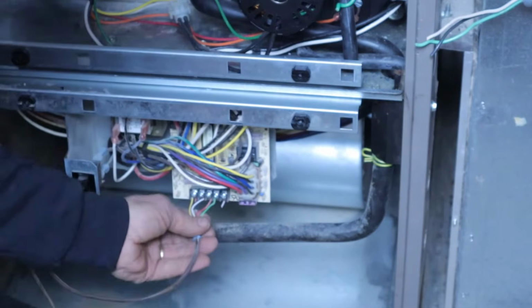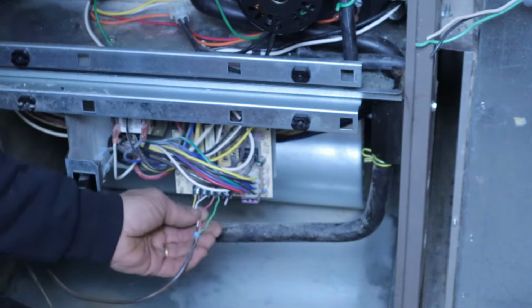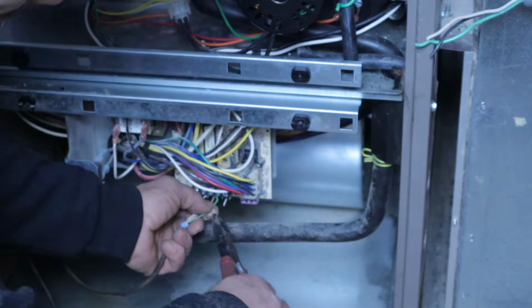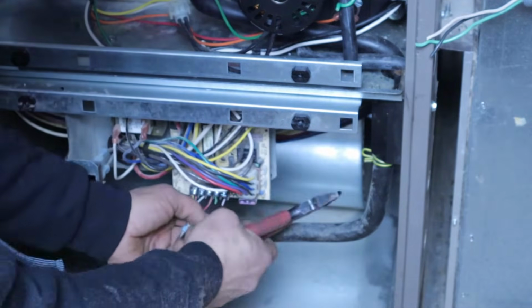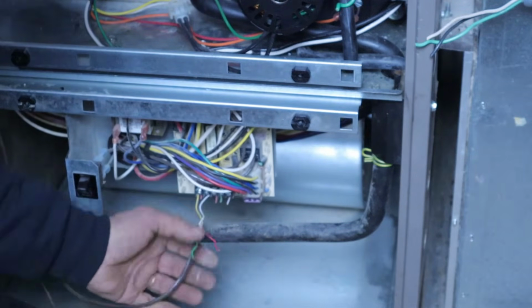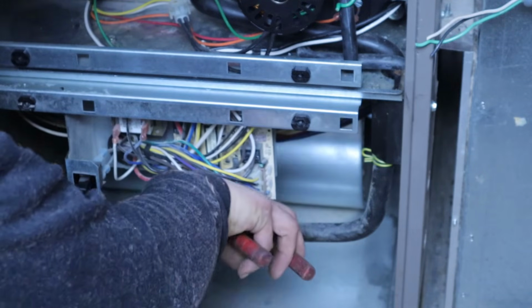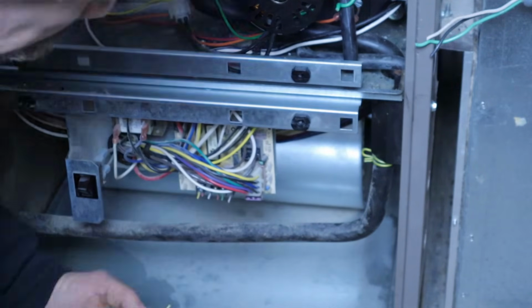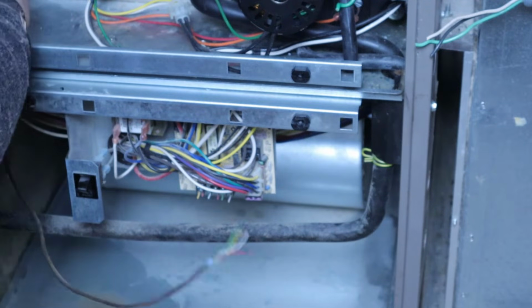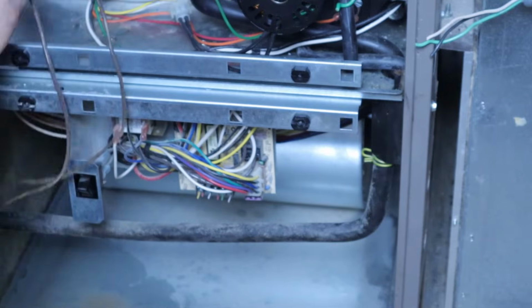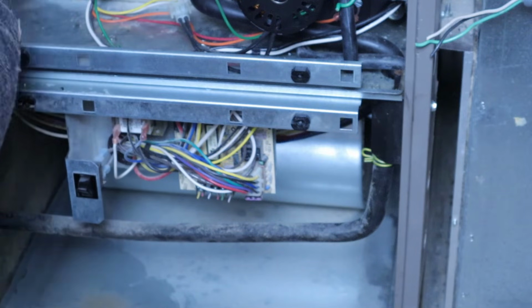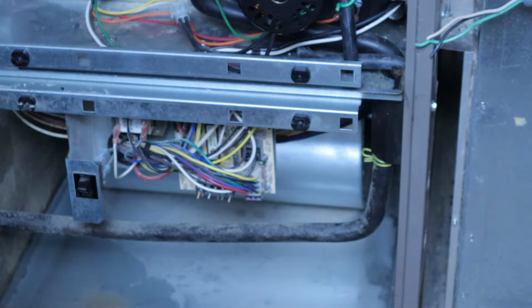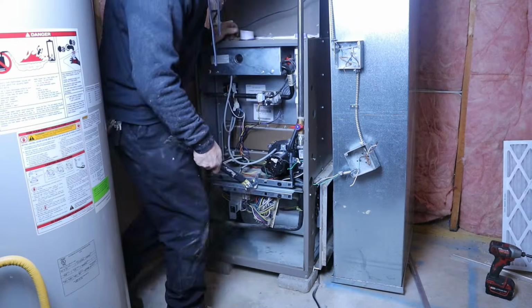And we have our 4 thermostat wires that go up to the thermostat. We have our green, that's our fan function on the thermostat. We got our red, which is our power, our white, which is our heating, and the yellow that is our cooling. So we got that disconnected. Pull those out. Alright, so now all we got to do is make sure this coil is well supported so that when we pull the furnace out, it doesn't fall down on us.